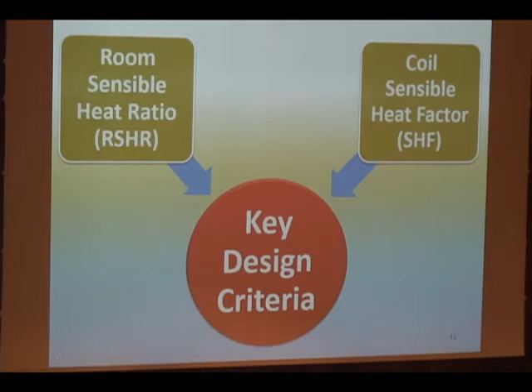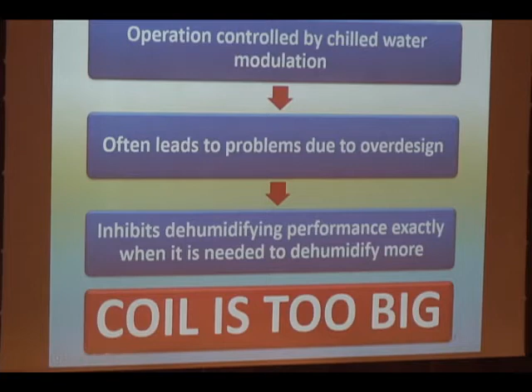With an oversized cooling system, which is generally the practice in most cases to handle peak cooling capacity, the coil ends up operating at reduced part-load conditions in the dynamic range, becoming ineffective at handling humidity loads. Simply put, the coil is just too big. If only I had the option of changing the coil at that stage, I'd be in a much better position to handle the humidity.